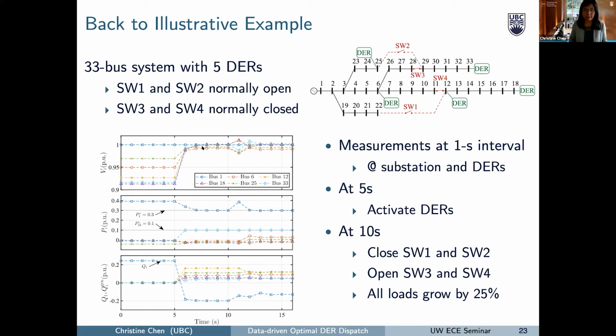After 5 seconds, we can see the voltage magnitude shoots up to 1 per unit. Then at 10 seconds, we changed the topology of the system by closing certain switches and opening others. We can see the proposed framework is able to update the estimated model and then implement the DER control so that the voltages are again close to 1 per unit. Here we can also regulate the power from the feeder head, as this line shows.